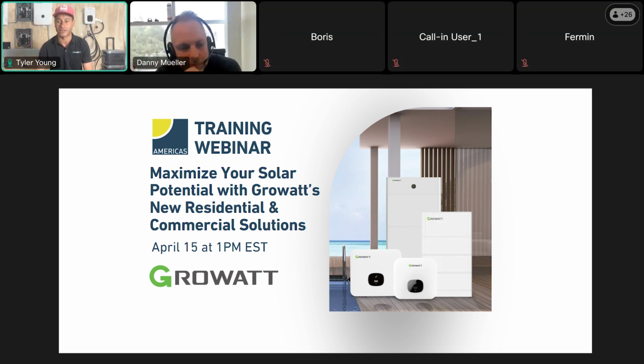So that's great. Just a general overview on the transfer switch and the parallel situation. Our high voltage MIN inverter right here behind me does pair with the 200 amp transfer switch. So those are always a bundle, and you can optionally choose to install the high voltage battery as well. But the MIN includes the 200 amp transfer switch, and parallel function is not currently available for that. It will be available later this year in 2025. But the SPH residential, off-grid, light commercial inverter that Fermin presented, the SPH 10K, does have an integrated transfer switch. So that would be just the inverter that you need to install instead of both the inverter and the 200 amp transfer switch. I think I made that a little bit more clear, hopefully.